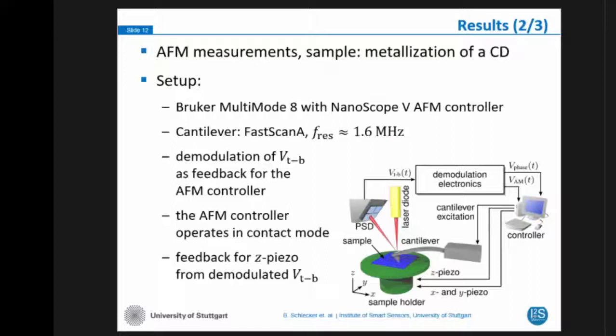For the AFM measurements, we used as a sample the metallization — the surface structure — of a compact disc. We used a commercial Multimode AFM from Bruker, which was not modified at all, with a Nanoscope 5 AFM controller, delivering a resonant frequency of approximately 1.6 MHz. We used our demodulation electronics to demodulate the top-minus-bottom signal from the deflection measurement, and fed our demodulated signal into the AFM controller, which then generated the feedback signal for the Z-piezo and reconstructed the image.